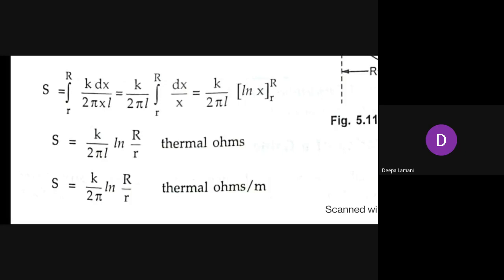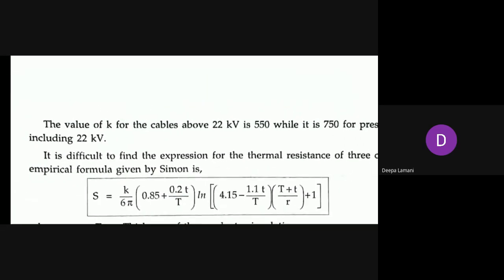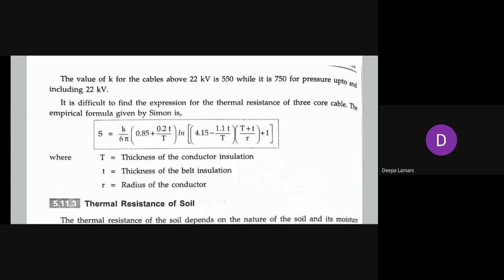The value of k is known for cables based on their material. For cables above 22 kV, k = 550, while for cables up to and including 22 kV, k = 750. The voltage rating determines which k value to use.